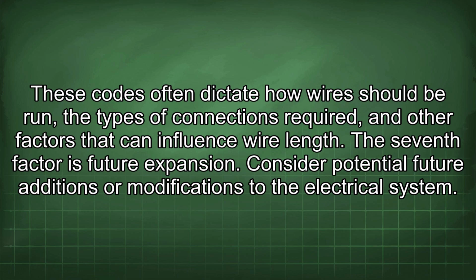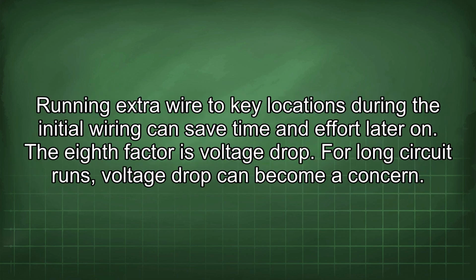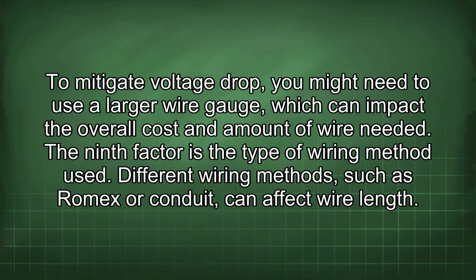The seventh factor is future expansion. Consider potential future additions or modifications to the electrical system. Running extra wire to key locations during the initial wiring can save time and effort later on. The eighth factor is voltage drop. For long circuit runs, voltage drop can become a concern. To mitigate voltage drop, you might need to use a larger wire gauge, which can impact the overall cost and amount of wire needed. The ninth factor is the type of wiring method used.